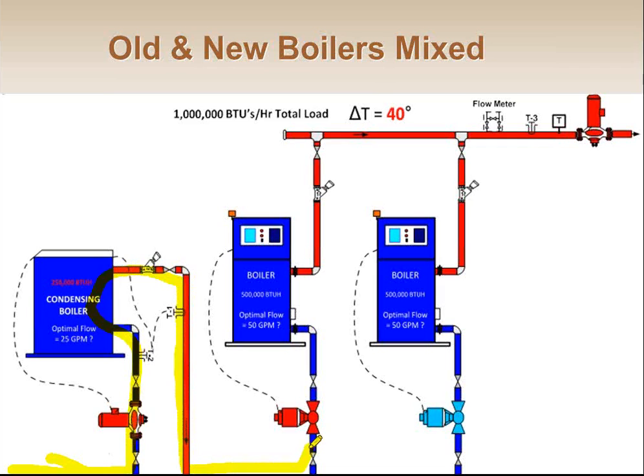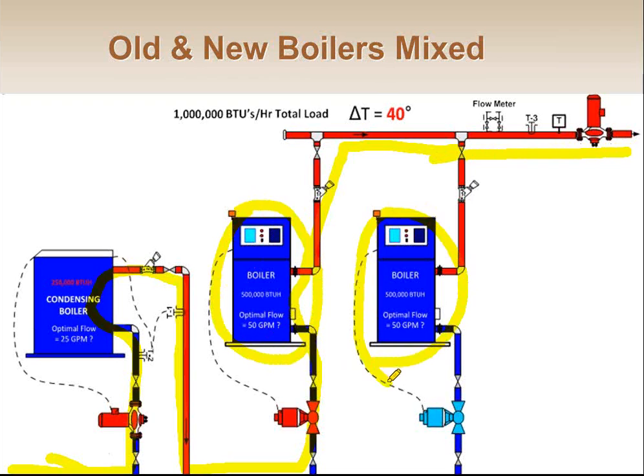And if that is good enough, it can flow right on to the other, out to the plant and out to the system. If it's not good enough, then number 2 boiler has to kick on, the old inefficient guy, and help me heat it up. And on really extreme days when it's minus 10 out, number 3 can kick on and help me out as well. In most of these cases, I can get 70 to 80% of my run hours on this little pony boiler that's 92, 93, 95% efficient, and I hardly ever have to turn the old boilers on.